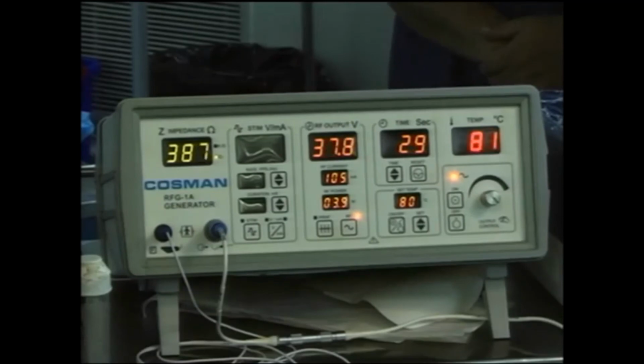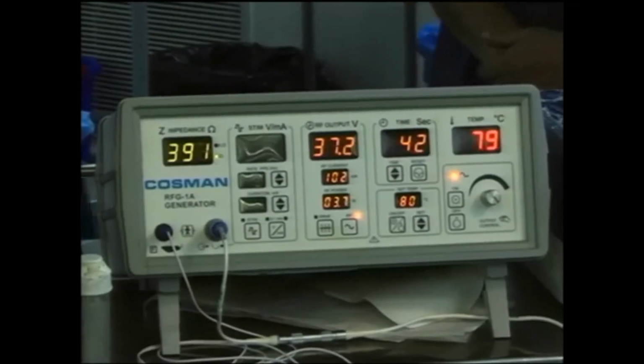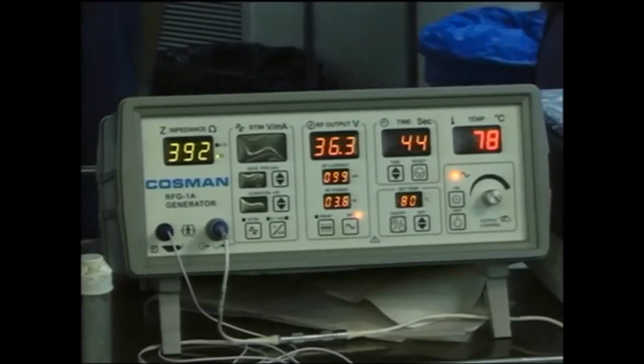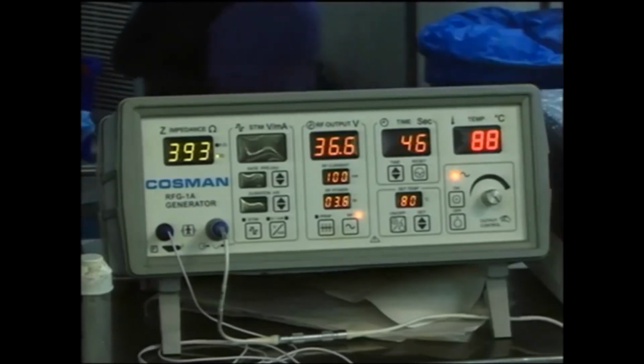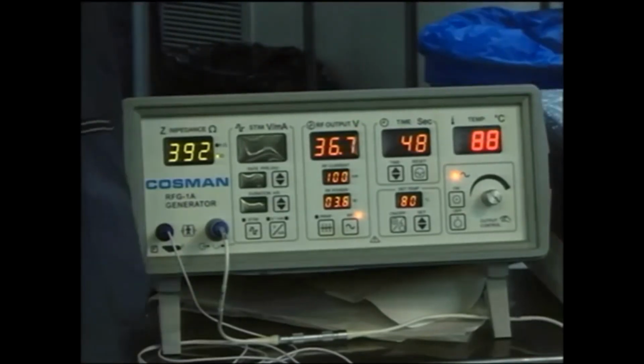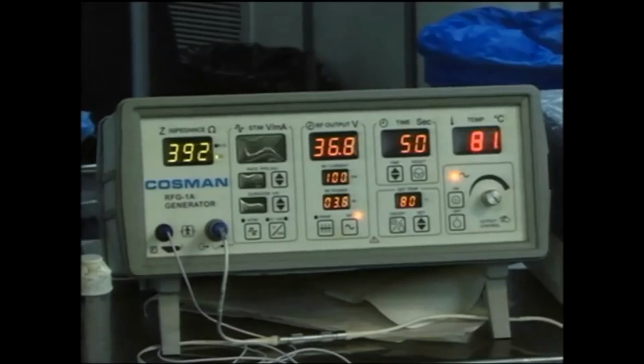And also this is a machine variability. In this machine you have to reset it once the temperature is reached. Whereas in neurotherm, the one that I use, if you set the temperature at, let's say, 80 degrees centigrade, only once 75 or 76 degrees is reached will the countdown start. Yes, some machines are like that. It will not be counting till the desired temperature is reached. So the actual time at the desired temperature should be 60 seconds or more.